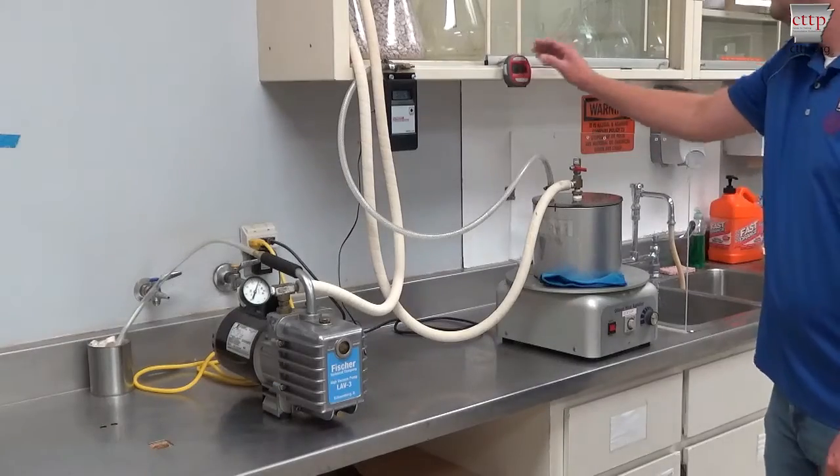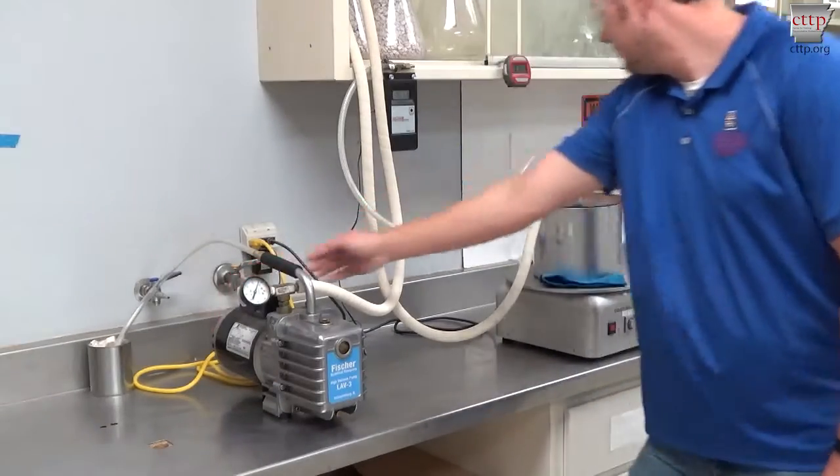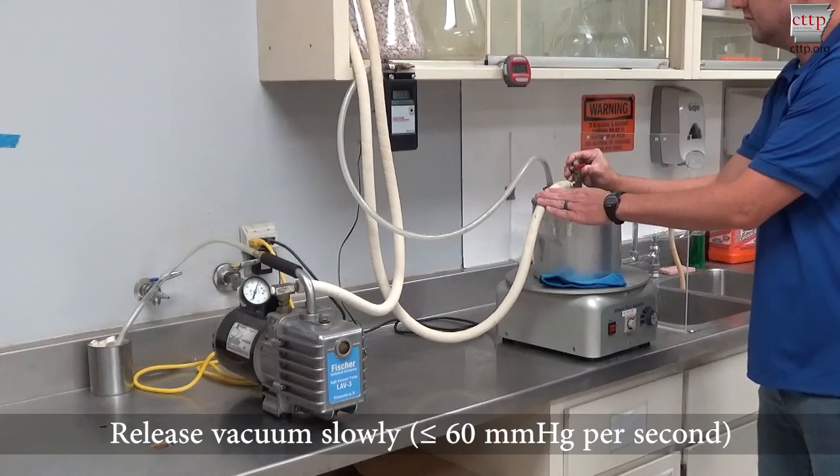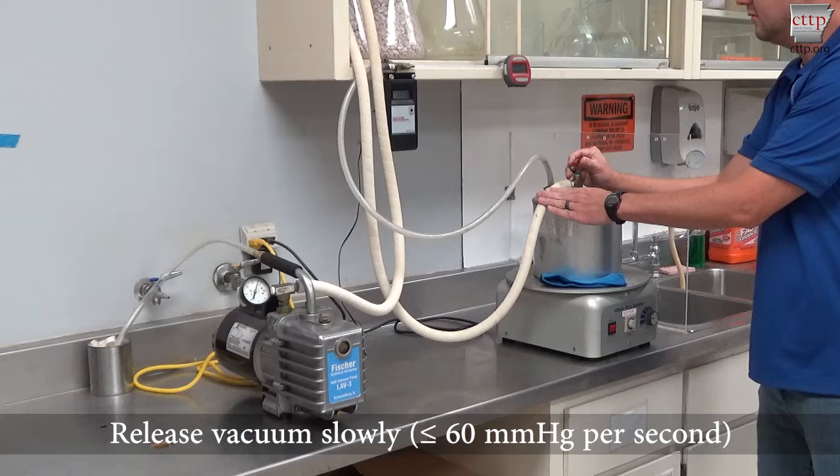When the vacuum period has elapsed, turn off the timer, vacuum pump, and mechanical agitator if used. If vacuum is complete, the water should no longer be boiling.